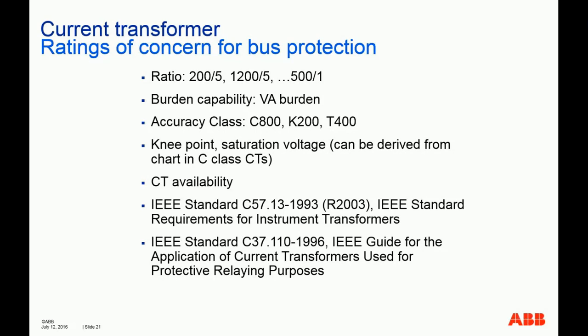And the K-class CT is similar to C. The difference between K and C is that the knee point voltage of the K-class CT is not less than 0.7, or 70%, of its rated voltage. So basically, for example, for the K200 indicated here, if it's considered a K-class CT, then the knee point voltage must be greater than 140 volts. Basically, that's what it says. And for T-type CT, it means its performance cannot be derived, cannot be interpolated from the excitation curve. The manufacturer has to provide the exact curve of this type of transformer.